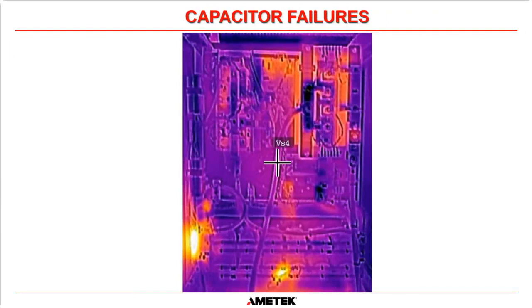And once again, you can see that there are DC capacitors mounted here. There's actually 2 banks of them. Ignore this; this is a resistor. It's actually the discharge resistor on the capacitor bank. So if you do power down your system, it will discharge those capacitors for you to make them safe. That's always going to be hot, and that's acceptable. But you can see that every single one of these DC capacitors is within the expected temperature. And that's the main way we find out if a capacitor is going to fail prematurely: it starts to heat up and it will be seen with an infrared camera.